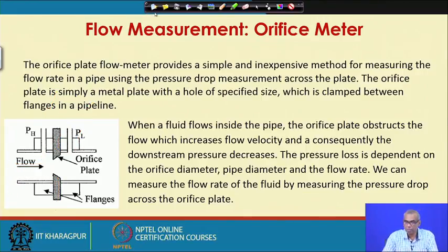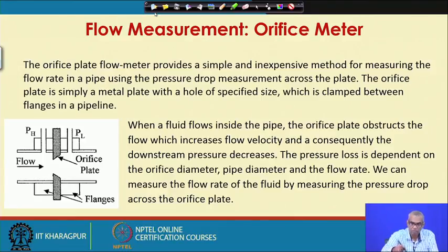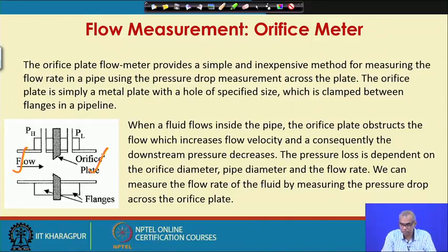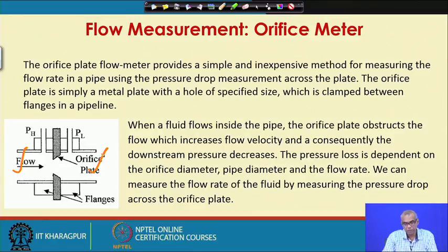When a fluid flows inside a pipe, the orifice plate obstructs the flow, which increases flow velocity and consequently the downstream pressure decreases. This is upstream and this is downstream. The pressure loss is dependent on the orifice diameter, pipe diameter, and the flow rate, but for a given orifice plate the pressure loss becomes dependent on the flow rate only.